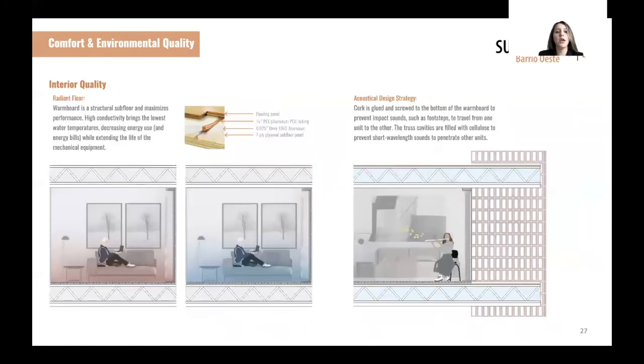Another strategy to increase the residents' comfort is radiant floor. The user is closer to the system, making it more efficient with less heating or cooling loads. Warmboard is a structural subfloor that maximizes performance because it has a high conductivity aluminum sheeting, using lower water temperatures and decreasing energy use while extending the life of mechanical equipment.